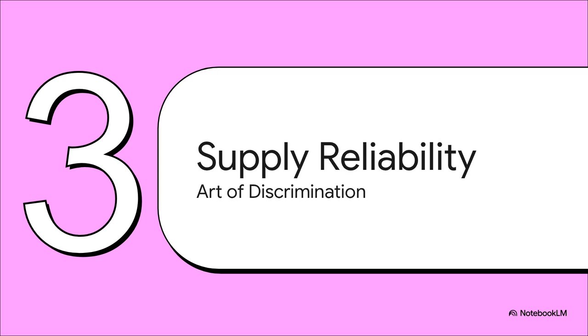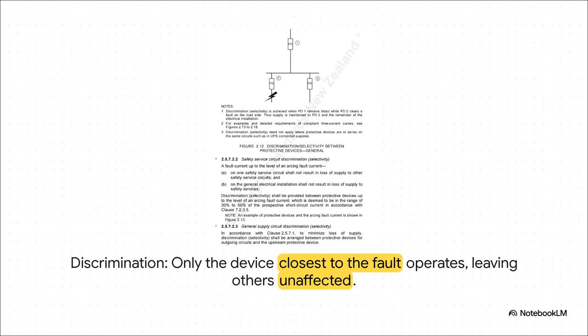Okay, so our cables are protected. Awesome. But what happens when a tiny fault happens on one little circuit? Do we really want the lights to go out in the entire building? Of course not. And that's where we have to design for reliability, using a concept called discrimination. The goal here is basically surgical precision. Just look at the diagram. If a fault happens downstream, we only want the device right next to it, PD2, to trip. We need the upstream device, PD1, to stay on, keeping the power flowing to all the other healthy circuits.